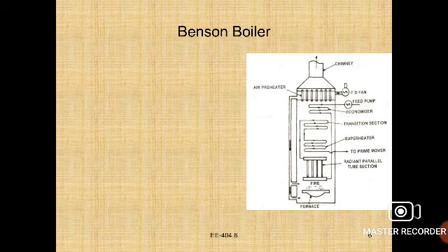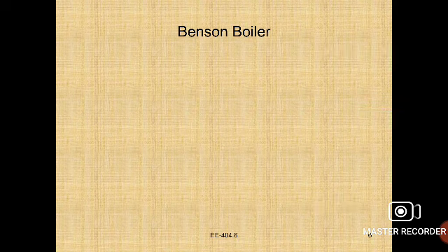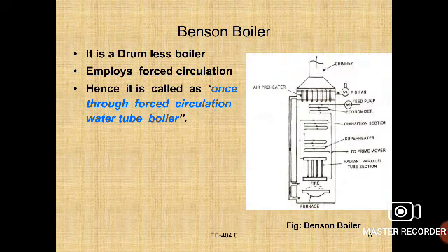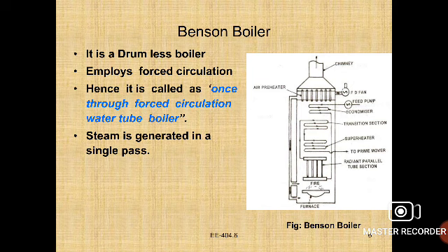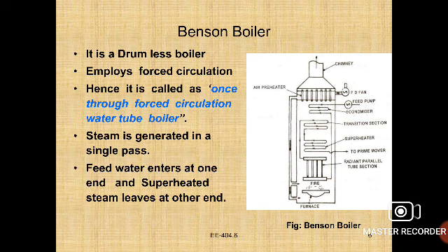Next, in the Benson boiler, the main thing is the drum. In the Benson boiler, the drum is completely eliminated, so we can call it drumless. It employs forced circulation, and steam is generated in a single pass.